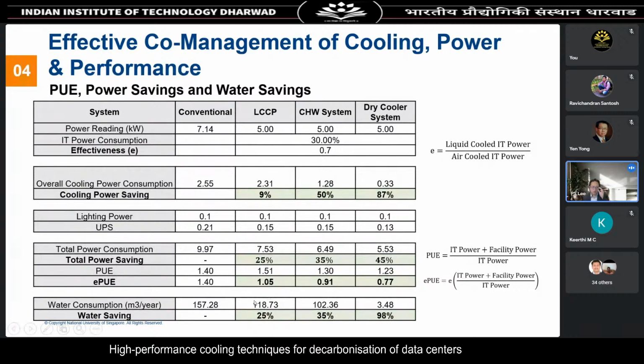I won't go into details since we're running a bit short of time, but quickly, some PUE numbers: conventional air-cooled data centers, quite efficient, have a PUE of about 1.4. But for our liquid cooling configurations, there are three of them, and some numbers actually look higher. You might think it doesn't make sense to switch from air-cooled to liquid cooling then. But why is it actually higher?